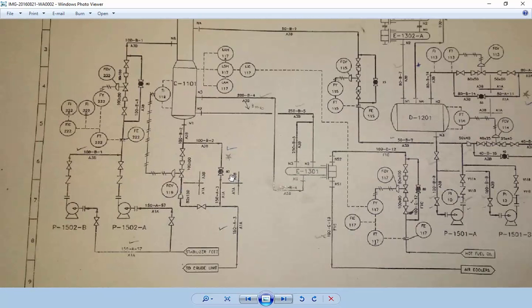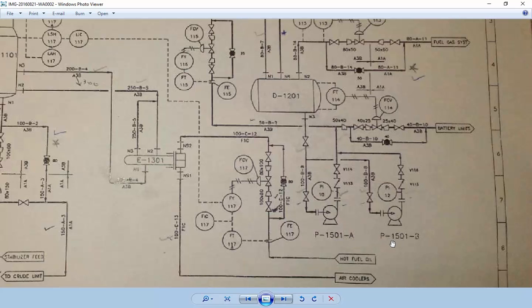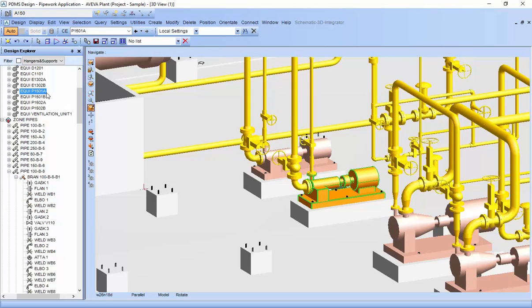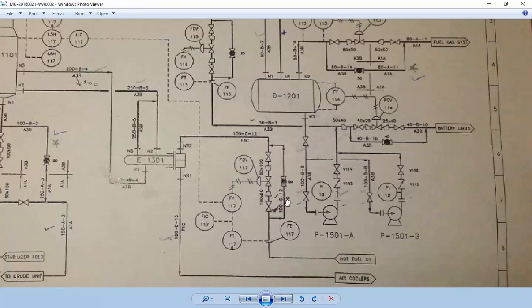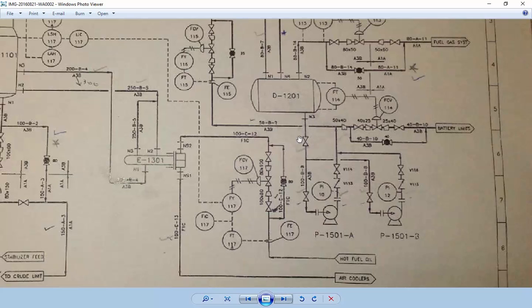Let's look at pumps P1501A and P1501B. Here we can see P1501A and P1501B. We can see there's a flange, then a valve. After this, both connect together, then there's another valve - actually the third valve - and it connects to N3, nozzle number 3.